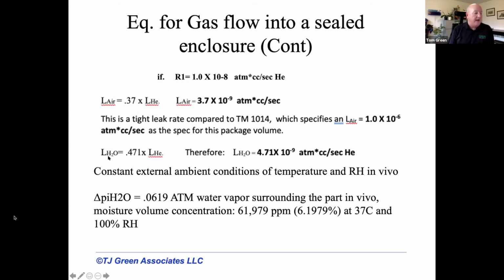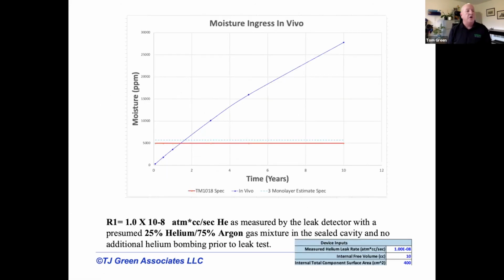Okay, and then from that, you can move over to a leak rate of water vapor going into the part. This is a part with a pretty tight leak rate, measured value 1 × 10⁻⁸. That's what the guy reads at the helium leak detector, with a presumed 25% helium backfill, no additional bombing, no more helium being pressurized into it.